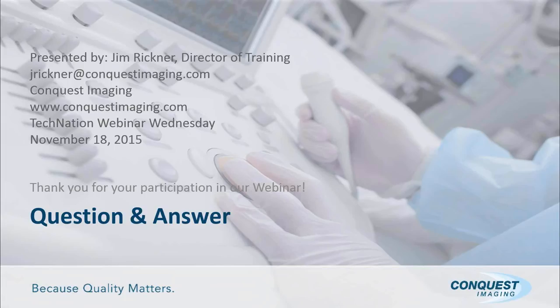Next question. Is there any error code access on the system? No, we have the ability to run a system confidence test, meaning that we can run a version of diagnostics. However, that version is a pass or fail, so it doesn't tell you specifically error codes. If the system is kicking an error code, there is no way, without Philips access, to go in and run any specific diagnostics against an error code at this time.